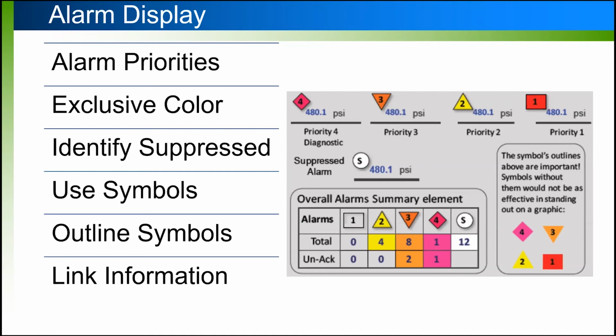When it comes to things like nuisance alarms, or when you take something out of service, like a motor, you don't want the alarms to sit there on your alarm screen. You don't want any animations associated with that alarm to keep reoccurring, especially if you have something like realarm enabled. You want to be able to shelve that alarm and show that you have an alarm shelved or suppressed for that particular piece of equipment or within that process. So that's another important thing.